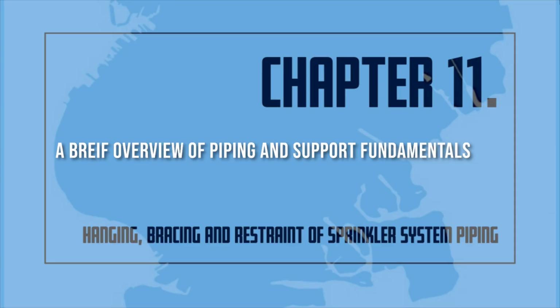For systems operating at less than 100 psi, the unsupported length between the end sprinkler head and the last hanger on the line shall not exceed 36 inches for 1 inch piping, 48 inches for 1 1/4 inch piping, and 60 inches for piping 1 1/2 inch or larger. For systems operating at pressures of 100 psi or greater, the hanger closest to the last sprinkler on the line shall be of the type that prevents the upward movement of the piping within the hanger assembly. This can be accomplished by the use of a surge restrainer.